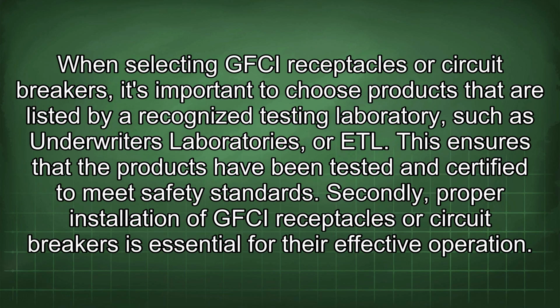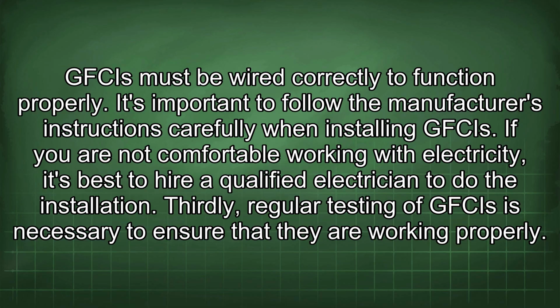electrical noise. When selecting GFCI receptacles or circuit breakers, it's important to choose products that are listed by a recognized testing laboratory, such as Underwriters Laboratories or ETL. This ensures that the products have been tested and certified to meet safety standards. Secondly, proper installation of GFCI receptacles or circuit breakers is essential for their effective operation. GFCIs must be wired correctly to function properly. It's important to follow the manufacturer's instructions carefully when installing GFCIs. If you are not comfortable working with electricity, it's best to hire a qualified electrician to do the installation.